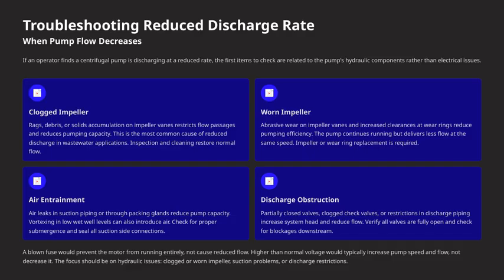When the impeller vanes experience abrasive wear or when the clearances at the wear rings increase, the pump becomes less efficient. It might still run, but it won't deliver the same flow rate. In such cases, replacing the impeller or the wear ring is necessary to bring performance back up. Air entrainment is also a common culprit. Air leaks in the suction piping or through packing glands can significantly reduce pump capacity. Additionally, vortexing in low wet well levels can introduce air. To fix this, check for proper submergence and seal all connections on the suction side to prevent air from entering.